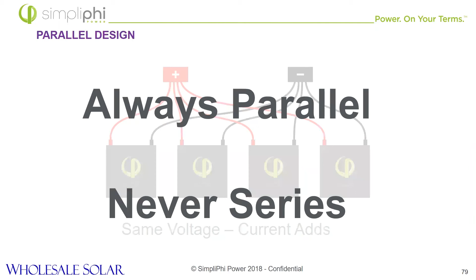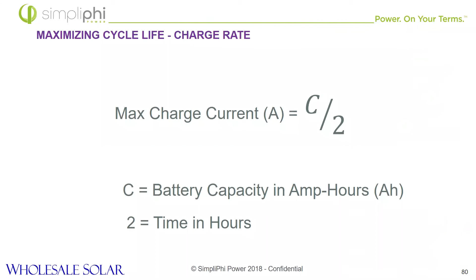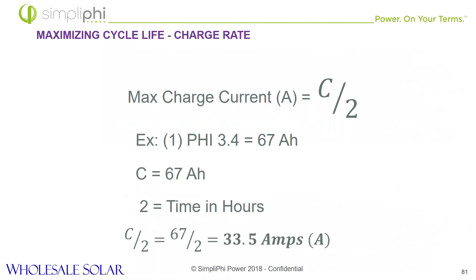There it is again, you'll hear that a lot of times. So C over 2 - it's actually a real simple calculation. The C is your numerator, and that is the capacity of the battery in amp hours, and 2 is the time in hours. So the calculation is this: 67 amp hours is one 3.4 battery at 48 volts. Divide by 2, you get 33.5 amps. So what we're saying is the max charge rate and max discharge rate you want to use is 33.5 amps for that particular battery.